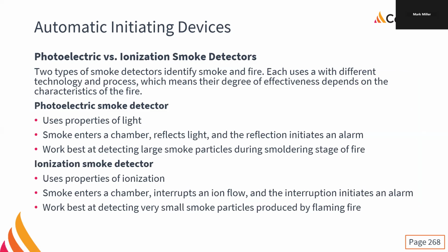There are two different types of smoke detectors: photoelectric and ionization smoke detectors. If we're looking at them installed on the ceiling, it can be really hard to tell which one is which. Unless you spend a lot of time with the specific manufacturers, you might be able to tell the intricacies of each. But if you take the head off the ceiling and look at the back, it's really easy to tell if we have a photoelectric or an ionization, because an ionization uses americium, which is radioactive. So there's going to be the radioactive symbol on the back. As soon as you see that, you know it's ionization.